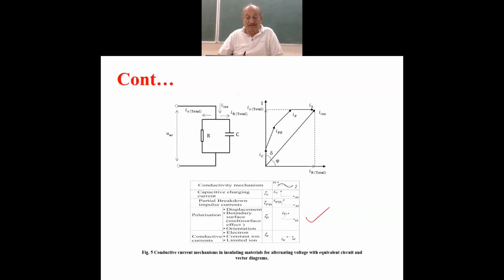The real power loss due to losses in the dielectric can be estimated knowing the dielectric loss factor, popularly known as tan delta, the angle delta formed between the insulation current and the capacitive branch of the current.